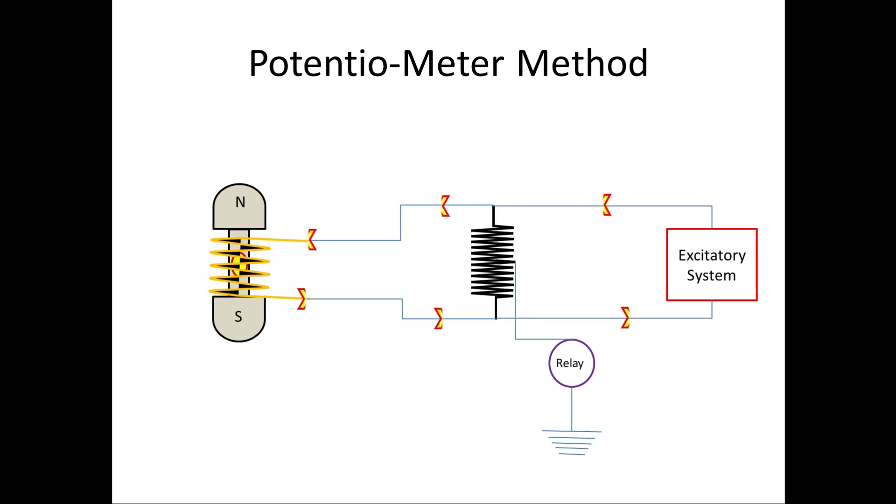Let us consider the rotor coil has earth fault. Now the current will get a path from the relay earthing point. Due to this high resistor ground, the fault current will not be very high, but the relay will detect the fault.